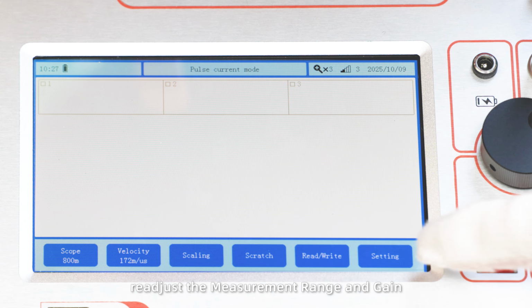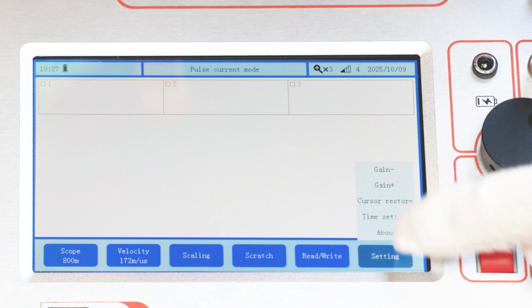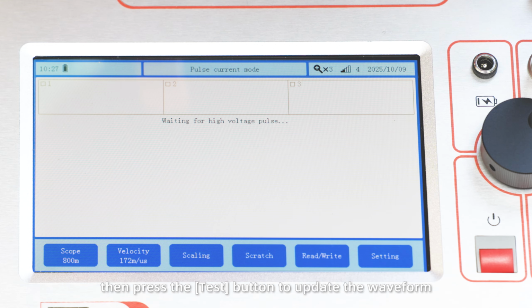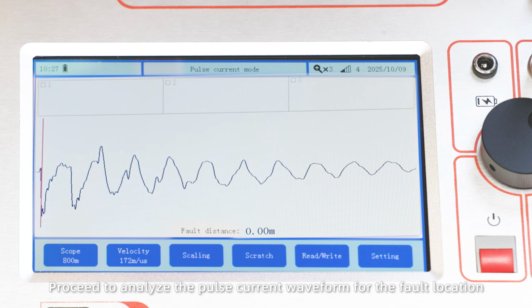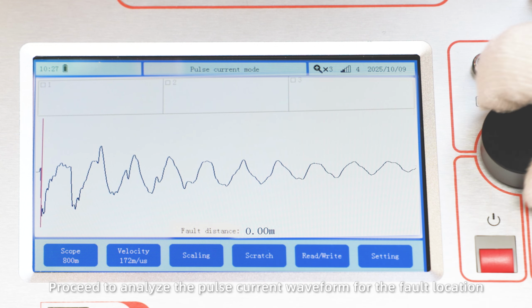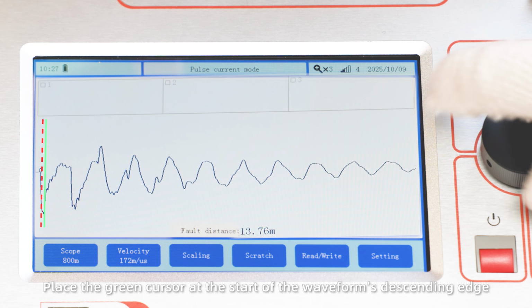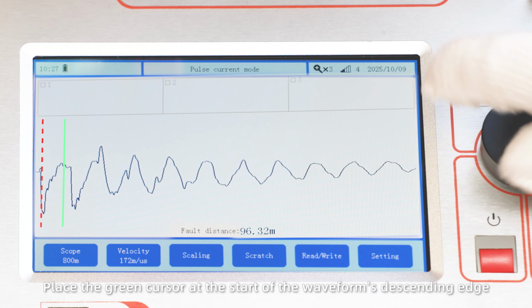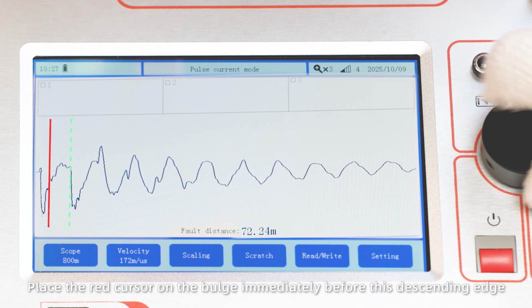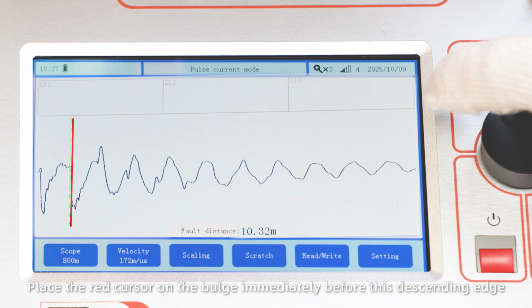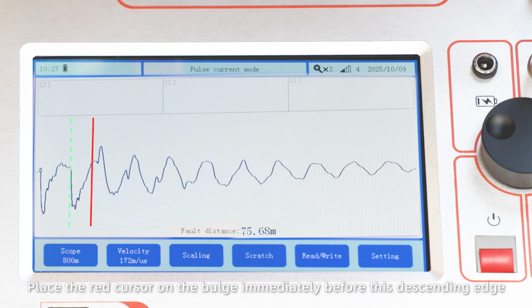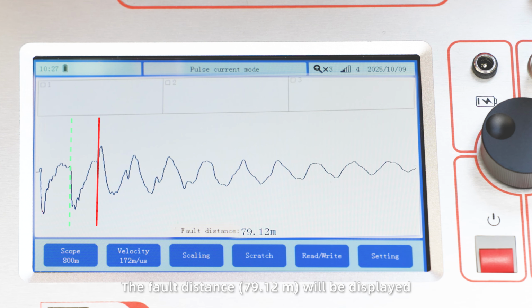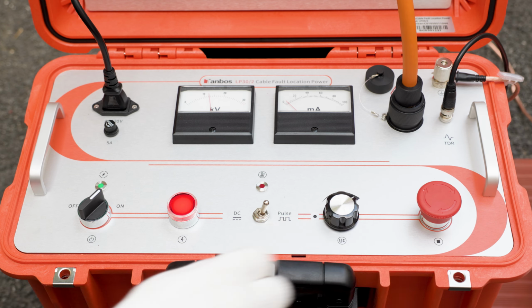If the pulse current waveform is not ideal, readjust the measurement range and gain. Then press the Test button to update the waveform. Proceed to analyze the pulse current waveform for the fault location. Place the green cursor at the start of the waveform's descending edge. Place the red cursor on the bulge immediately before this descending edge. The fault distance, 79.12 meter, will be displayed.